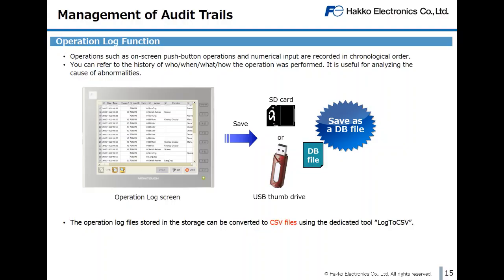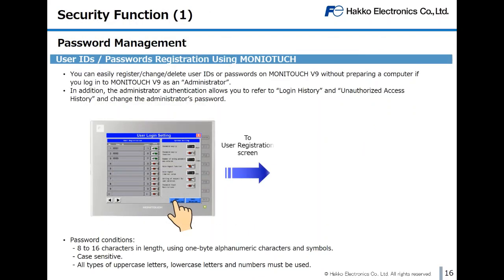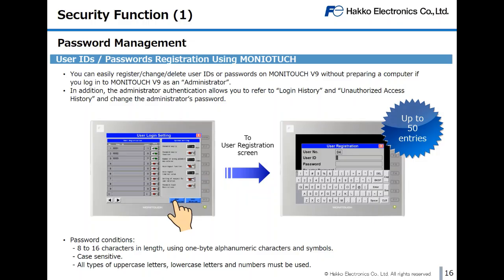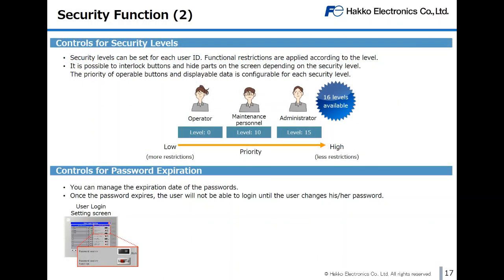As for security function, we prepared the component parts in order to comply with the requirements of Part 11. The password policy of this component parts is 8 to 16 characters in length. Case sensitive. Combination of uppercase letters, lowercase letters, and numbers. Password expiration setting is available.